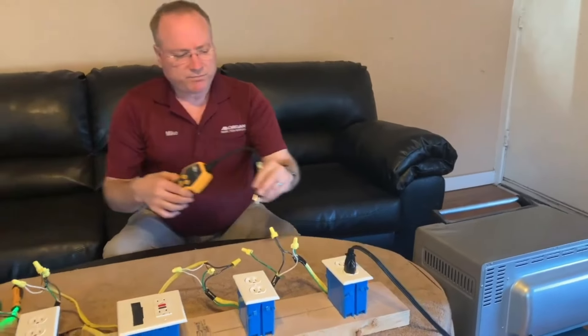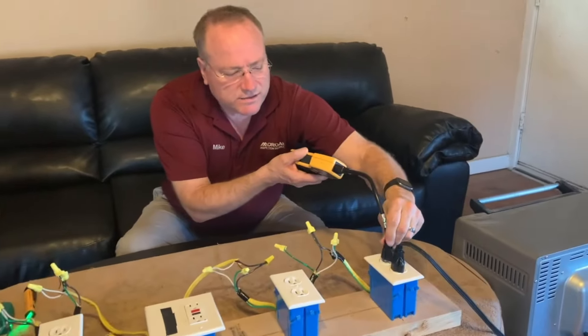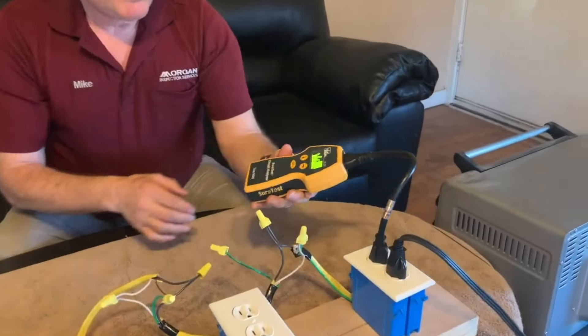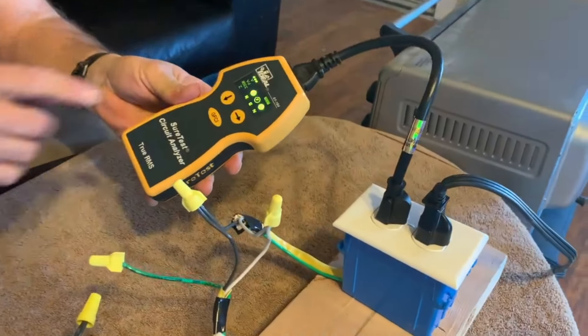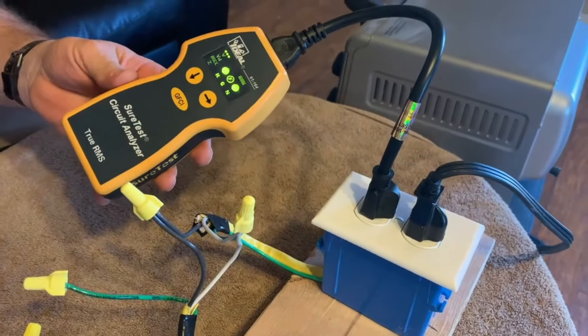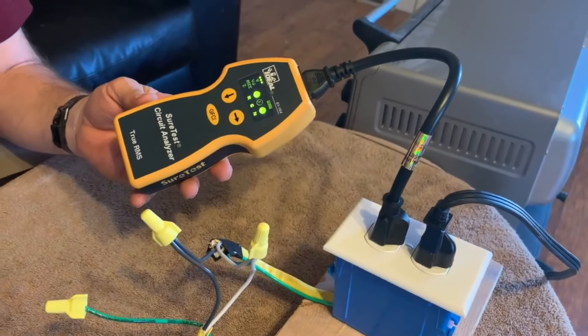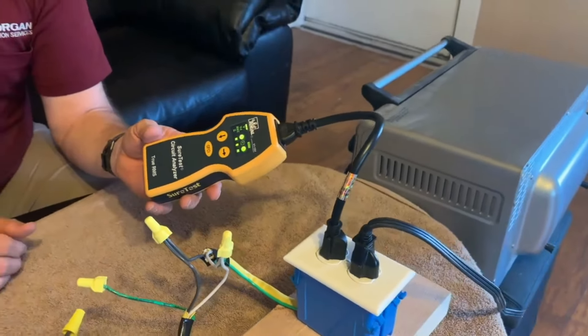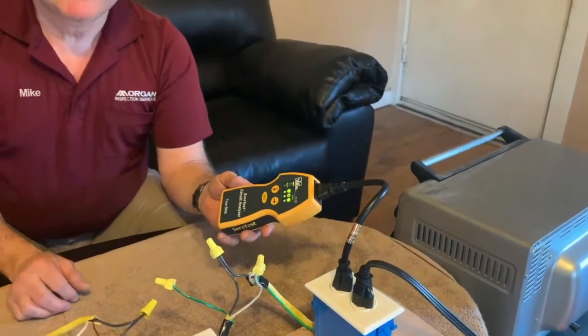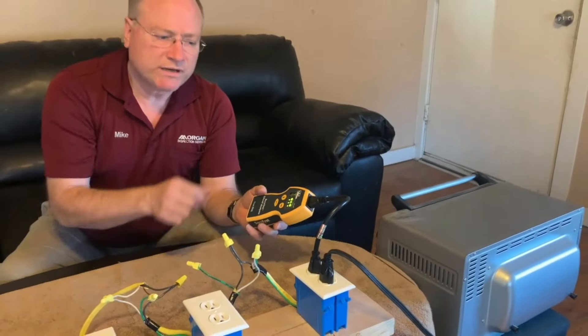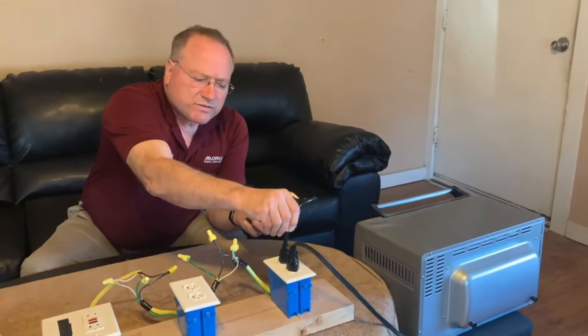So if I plug in my SureTest circuit analyzer into this same electrical outlet, you'll see this F flashing. That flashing F indicates that it's a false ground. So this circuit analyzer does pick up the fact that this outlet does have a bootleg ground. But let me show you why these are so dangerous.